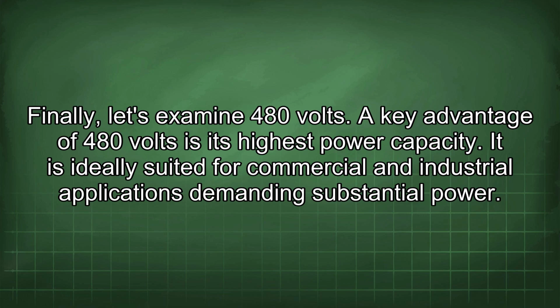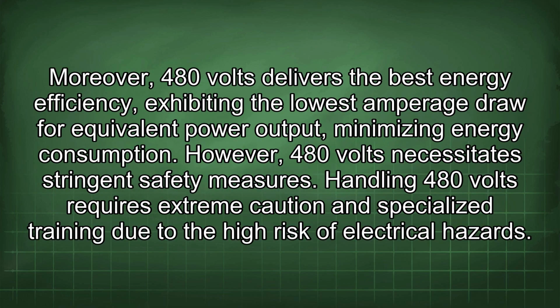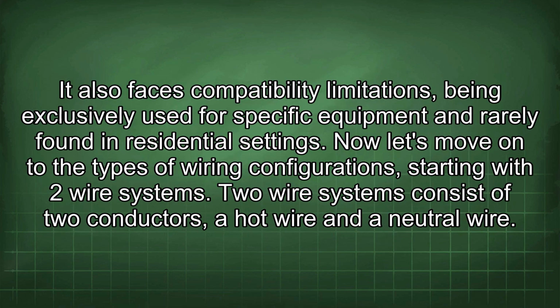A key advantage of 480 volts is its highest power capacity. It is ideally suited for commercial and industrial applications demanding substantial power. Moreover, 480 volts delivers the best energy efficiency, exhibiting the lowest amperage draw for equivalent power output, minimizing energy consumption. However, 480 volts necessitates stringent safety measures. Handling 480 volts requires extreme caution and specialized training due to the high risk of electrical hazards. It also faces compatibility limitations, being exclusively used for specific equipment and rarely found in residential settings.